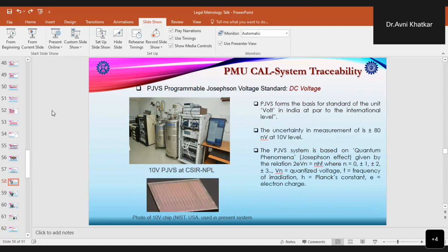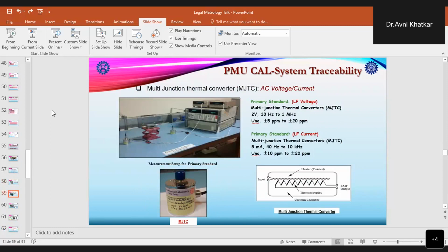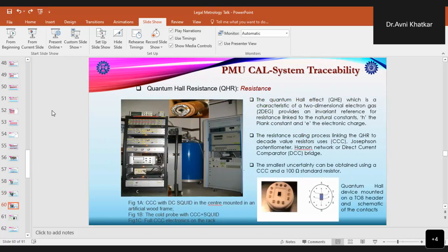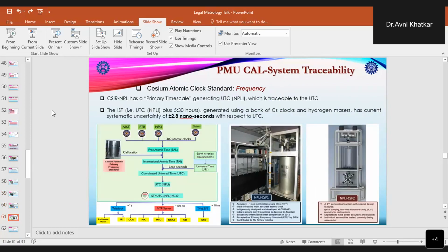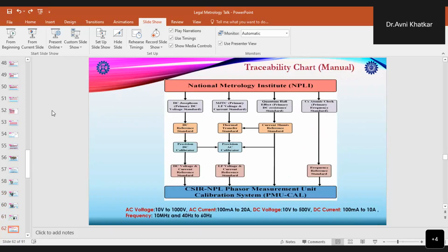Just to see a glimpse, this is the PJVS, the programmable Josephson voltage standard, for the DC voltage traceability of the system. These are the MJTCs for the AC voltage and current. For the resistance, we have the quantum Hall resistance standard. For the frequency, we have cesium atomic clock standards. This chart shows the traceability chart of the PMU calibrator system: for the AC voltage, a range from 10 volts to 1000 volts; AC current from 100 milliamperes to 20 amperes; DC voltage 10 volts to 500 volts; DC current 100 milliamperes to 10 amperes; and frequency at 10 megahertz and from 40 hertz to 60 hertz.